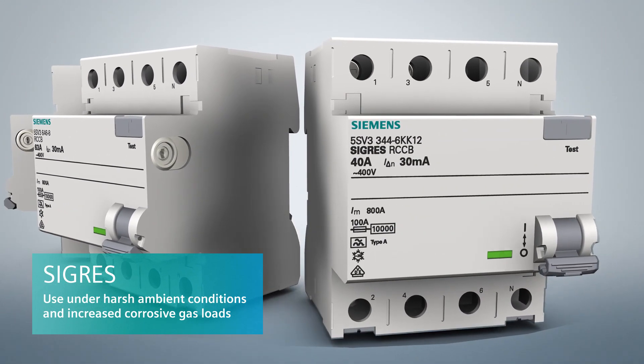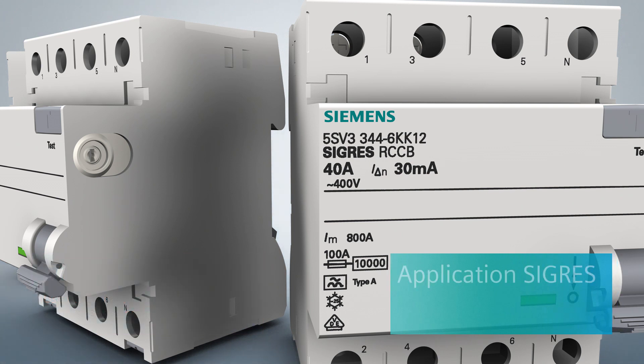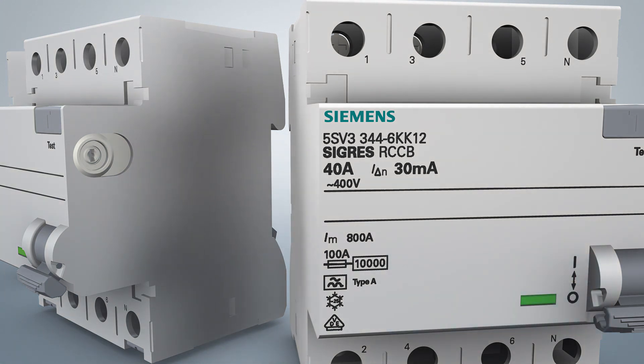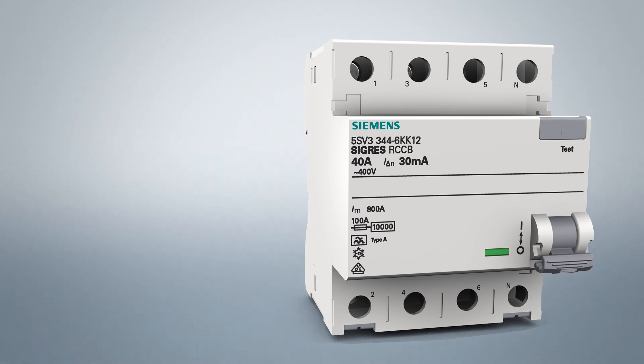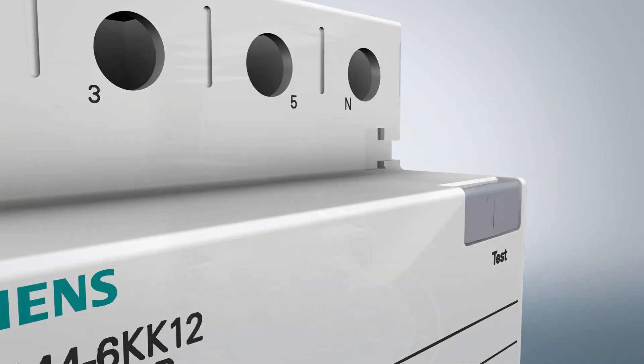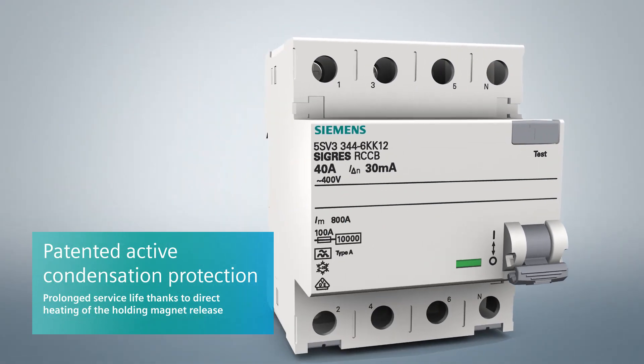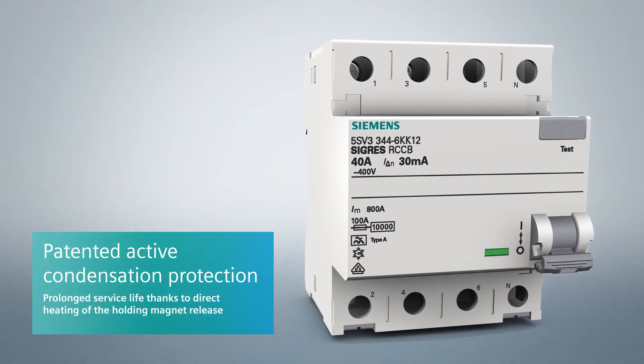The SIGRES residual current protective device was developed for severe ambient conditions with increased corrosive gas loads. Gases in connection with humidity, which frequently occur in indoor swimming pools, agriculture and chemical industry applications, bear a corrosive effect on the device's metal parts and particularly on the metal surfaces of the holding magnet release. The SIGRES device prevents the formation of corrosion with its patented active condensation protection. The direct heating of the holding magnet release with minimum power input ensures a slightly increased temperature on the metal parts, which considerably prolongs the device's service life.